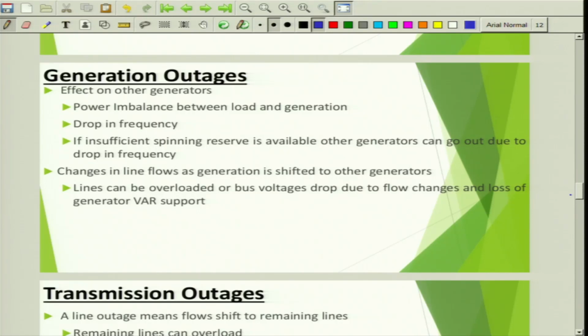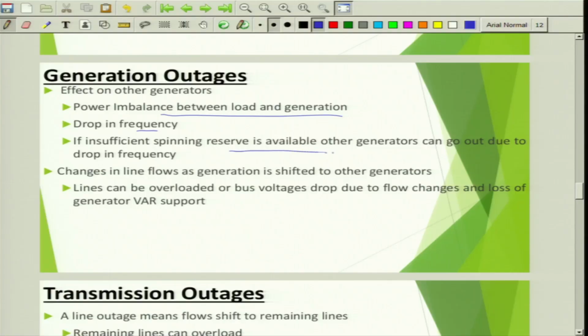So then there are generator outages, we spoke about line outages. The 3 possible reasons can we say there: power imbalance between load and generation, right, and there is a drop in frequency. This can have effect on other generators. If there is imbalance between power, then one generator could be overloaded, another generator may not be much loaded, and there is a drop in frequency, then the remaining generators have to cater to the requirement. If there is one generator dropped because of which there is a drop in frequency and there is burden on the rest of the generators, there is an effect on other generators, and if insufficient spinning reserve is available, other generators can go out due to drop in frequency. This lack of spinning reserve is another reason, right?